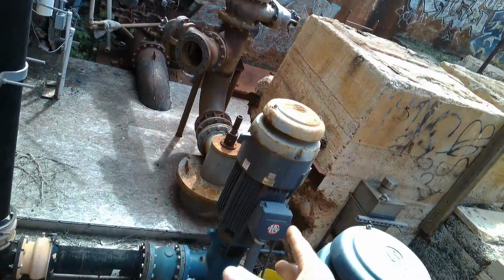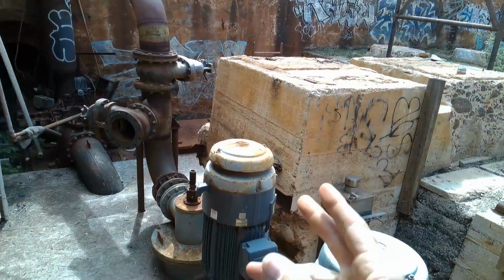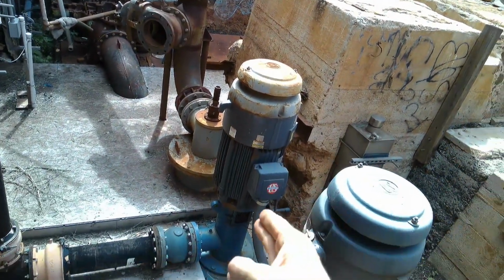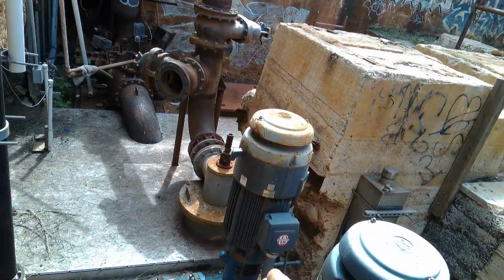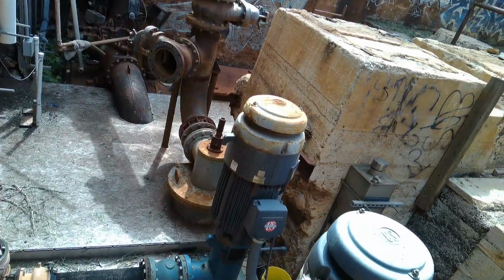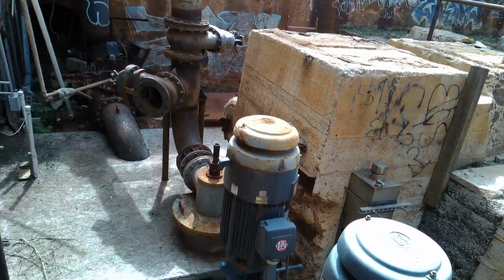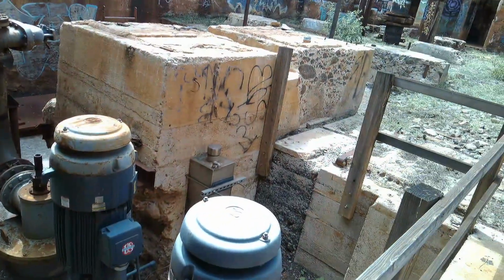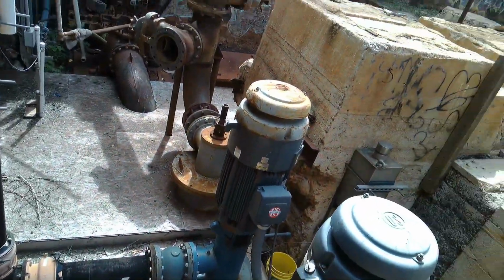Because if there's a dead short in the peckerhead, then the motor might be okay and we can save it. But if there's no dead short or arcing in the peckerhead, then it's inside the windings of the motor and she's dead. And the customer's going to have to look at either rewinding it or replacing it.